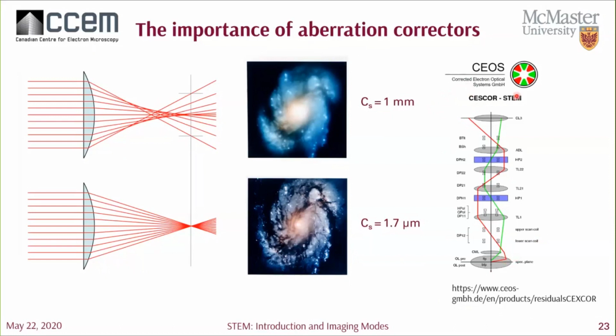While it's still possible to obtain atomic images without correctors, we can see the benefits of aberration correction. With the smaller probe formed from the correctors, you can see that the contrast is brighter in the image as compared to the uncorrected image. Correctors also provide an advantage in that they form a brighter probe due to the fact that the probe is smaller. This means that we can increase scattering in our sample and therefore increase the signal that we collect, giving us a better signal to noise ratio.